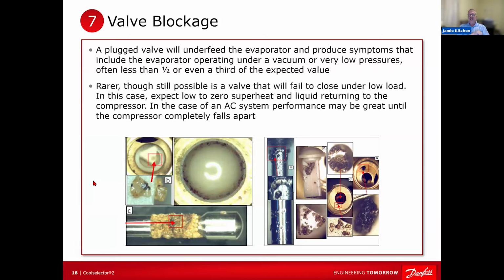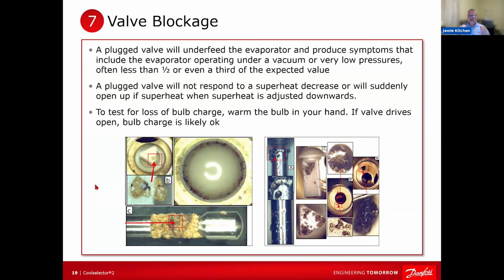And so what ends up happening is if you put a bit of acid neutralizer in, fine. We got no problem with that. But if you put 5 times as much as what you're supposed to have in there, now you're going to have an issue because it's going to start reacting with things and you're going to produce some salt. And these can basically start causing problems. And it doesn't take much before you plug that TXV up. So again, this stuff works.